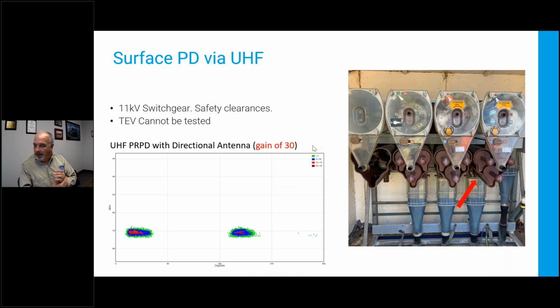Here is an example of the UHF in action. So this is some weird Australian switchgear. I've never even seen anything like it. But it's not enclosed in metal. It's actually behind a fence. So I can't do TEV. It's something occurring inside, so I can't do ultrasonic. There's no way to get to the ground straps down here. I could have picked it up on these ground straps, but they don't have RFCTs installed, so I can't get in there. It's not safe.